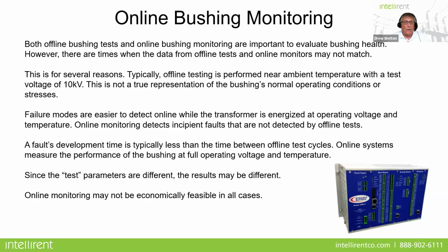Online monitoring can detect incipient faults that are not detected by offline tests. A fault's development time is typically less than the time between offline test cycles. Online systems measure the performance constantly, and since these test parameters are different, the results may be different.